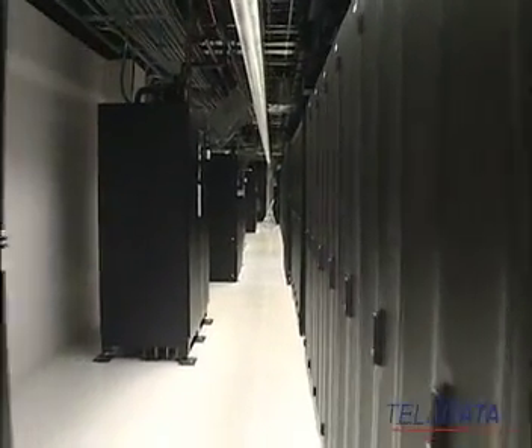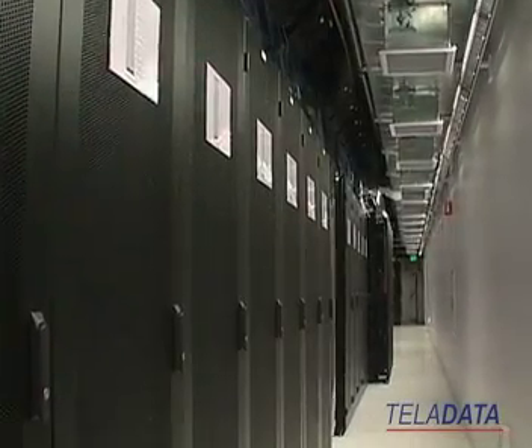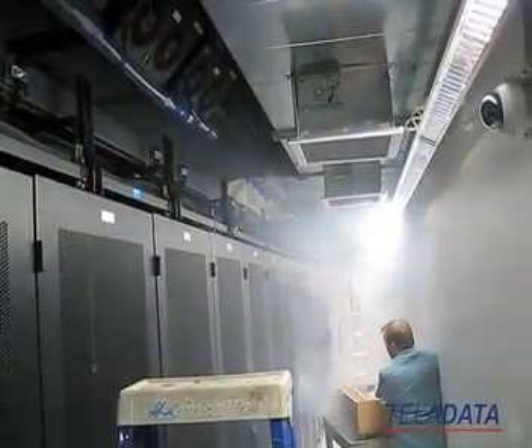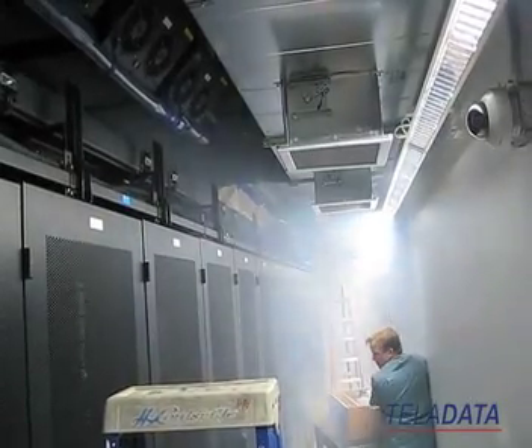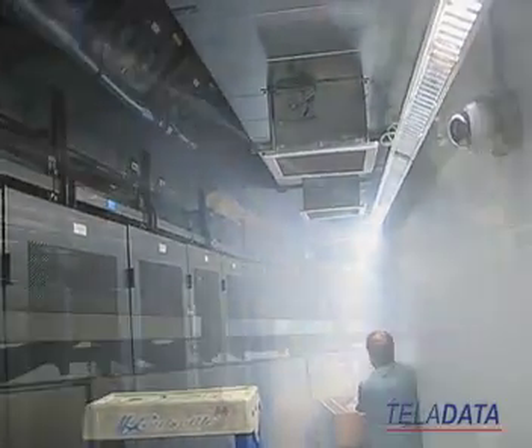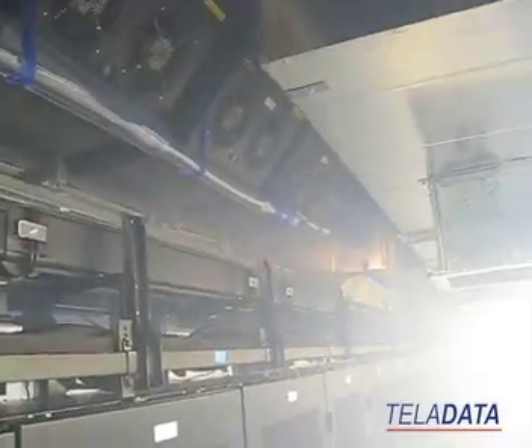We also recognized that there was a high probability that we were going to have short cycling occurring. In other words, the cold air from this side mixing with the hot air on the hot aisle before it ever had a chance to go through the server cabinets. And then we had our general contractor bring in a smoke producing machine, and sure enough, the smoke did show an airflow pattern of short cycling.